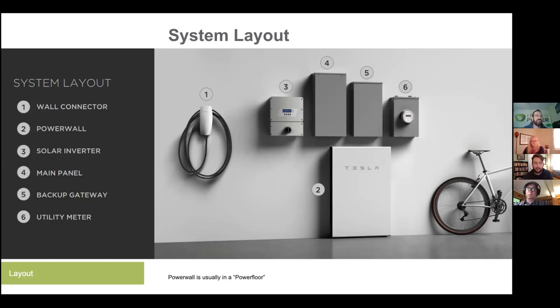These are all on a case-by-case basis because everyone's house is a little different. Maybe you've got stuff in the garage that you can't move. Maybe you have a spot in the basement where you would ideally like the batteries to go. However, these batteries need to be in a non-livable space. A lot of times people have finished basements with a room they never use that they think would be a good spot. To pass fire code, this needs to be in an unfinished basement setting, a garage, or an exterior part of the house. Even in an unfinished basement, the battery needs to be on an exterior wall of the house.